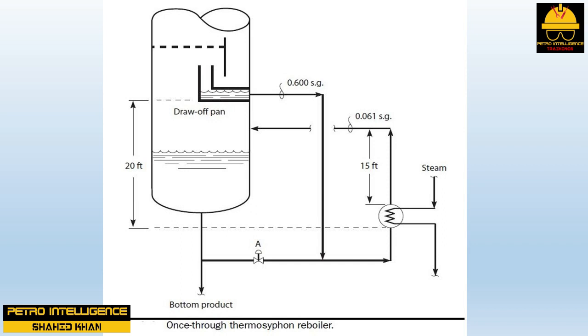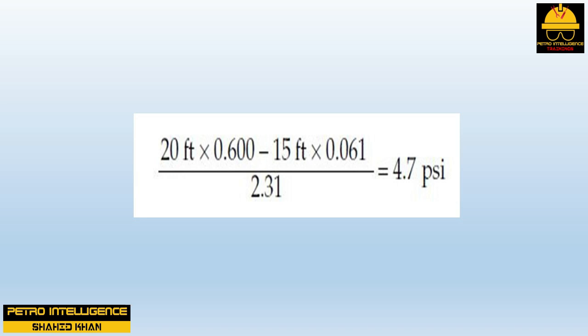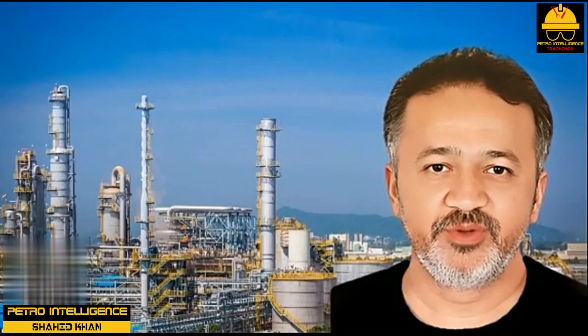This picture shows a once-through thermosyphon reboiler. The driving force to promote flow through this reboiler is the density difference between the reboiler feed line and the froth-filled reboiler return line. For example: specific gravity of liquid in the reboiler feed line is 0.600, height of liquid above the reboiler inlet is 20 feet, mixed-phase specific gravity of the froth leaving the reboiler is 0.061, and height of the return line is 15 feet. The differential pressure driving force is then (20 × 0.600 − 15 × 0.061) / 2.31 = 4.7 psi.